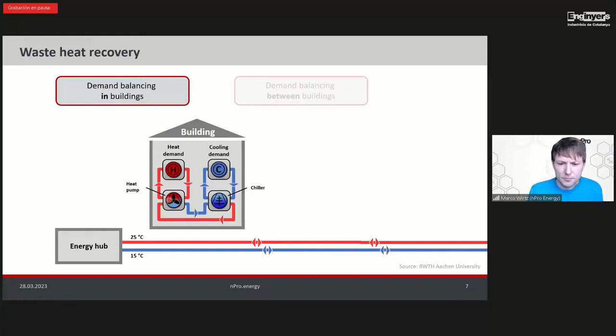It could also be that we have a domestic hot water demand in the building, and that's the reason why we have heating and cooling demands at the same time. So a few scenarios are thinkable. And then we can use the waste heat from the cooling application directly for the heat pump in the building, and we don't need any further energy from the network. So that's the first effect in such a network, that we can directly balance heating and cooling demands within a building. And the second effect is that we can also balance heating and cooling demands between buildings.